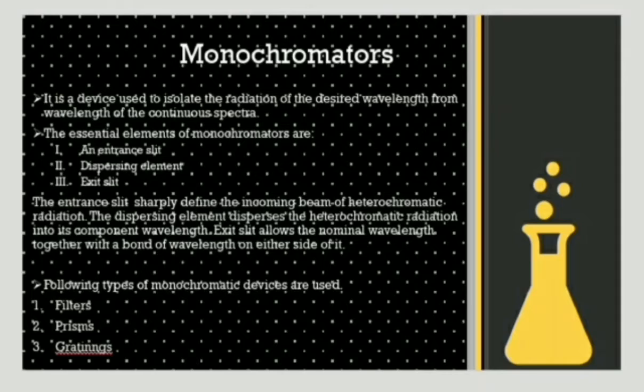The next instrumentation component is the monochromator, which converts light — a mixture of several photons and radiations — into a simple beam of a single wavelength. The essential elements of monochromators are an entrance slit, dispersing element, and exit slit. The entrance slit sharply defines the incoming beam of heterochromatic radiations. The dispersing element disperses the heterochromatic radiations into component wavelengths. The exit slit allows the nominal wavelength together with a band of wavelengths on either side. The types of monochromatic devices are filters, prisms, and gratings.